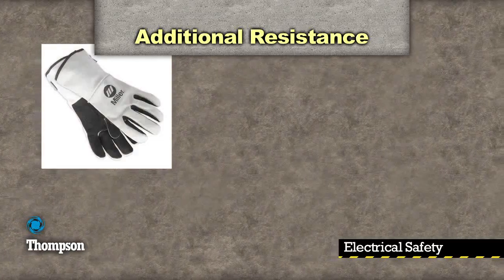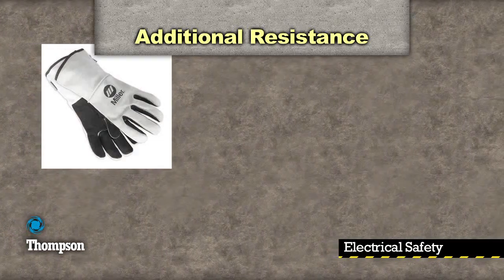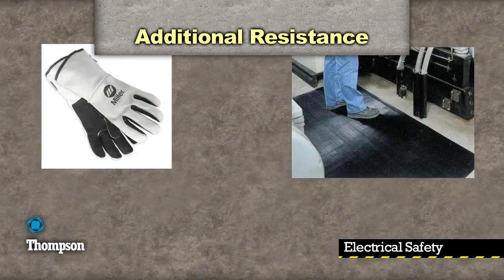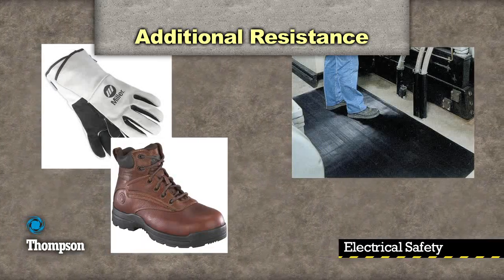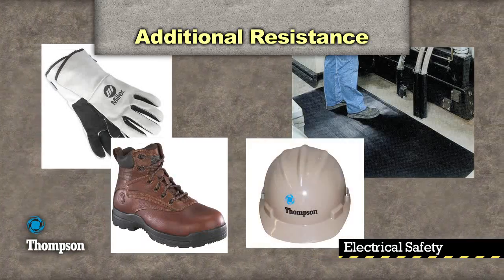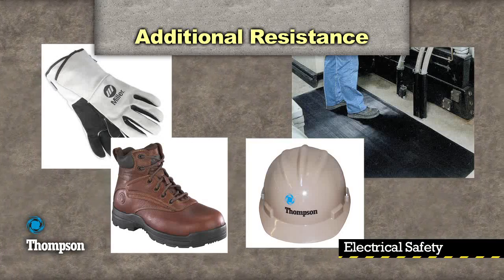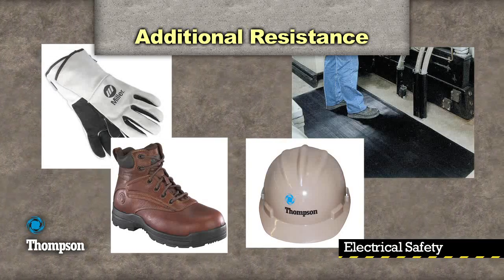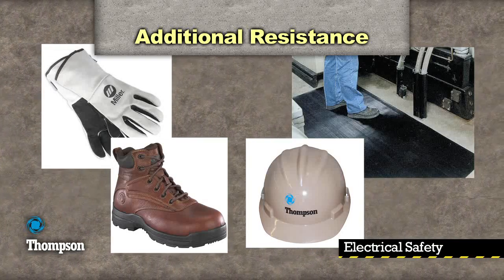The primary way to protect yourself from electrical hazards is by using PPEs that increase the resistance offered by the body, thus decreasing the number of milliamps you're exposed to. Of course, you'll want to make sure that the PPE being used is properly rated for the voltage that you may be exposed to.